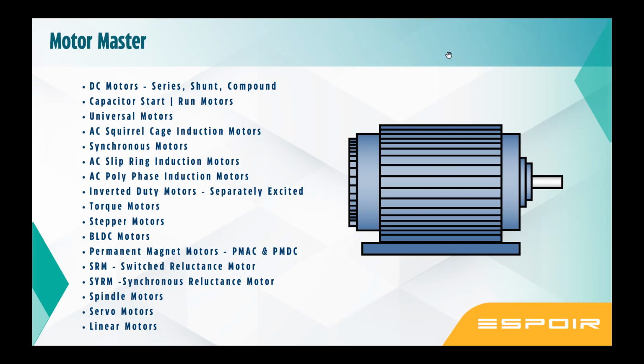Then there are some slip ring induction motors. There are some inverter duty motors for better efficient running through a VFD. Then synchronous reluctance motors and switched reluctance motors are slowly replacing induction motors in certain applications. Permanent magnet AC motors are replacing them in certain applications where efficiency, speed, and precision are involved. Servo motors and linear servo motors are taking place in many robotic, special purpose machines, and laser and plasma machines. They are completely getting into servos. So that's an overall idea about the types of motors available. Our focus is going to be on the squirrel cage induction motor, which is 90% or slightly over 90% of what you see in the industrial environment.